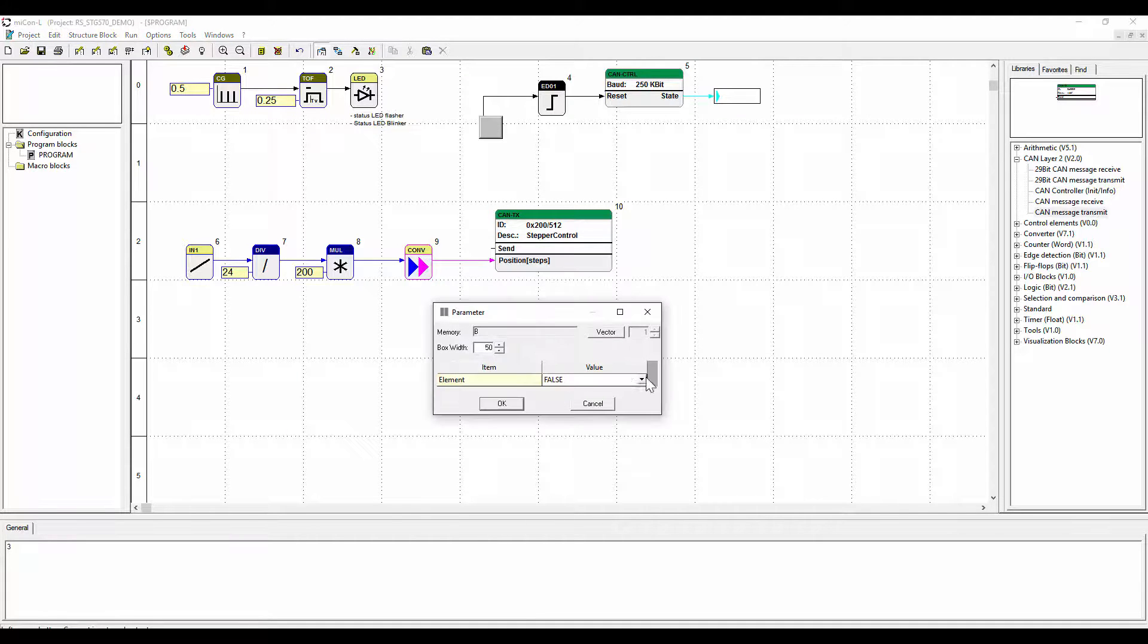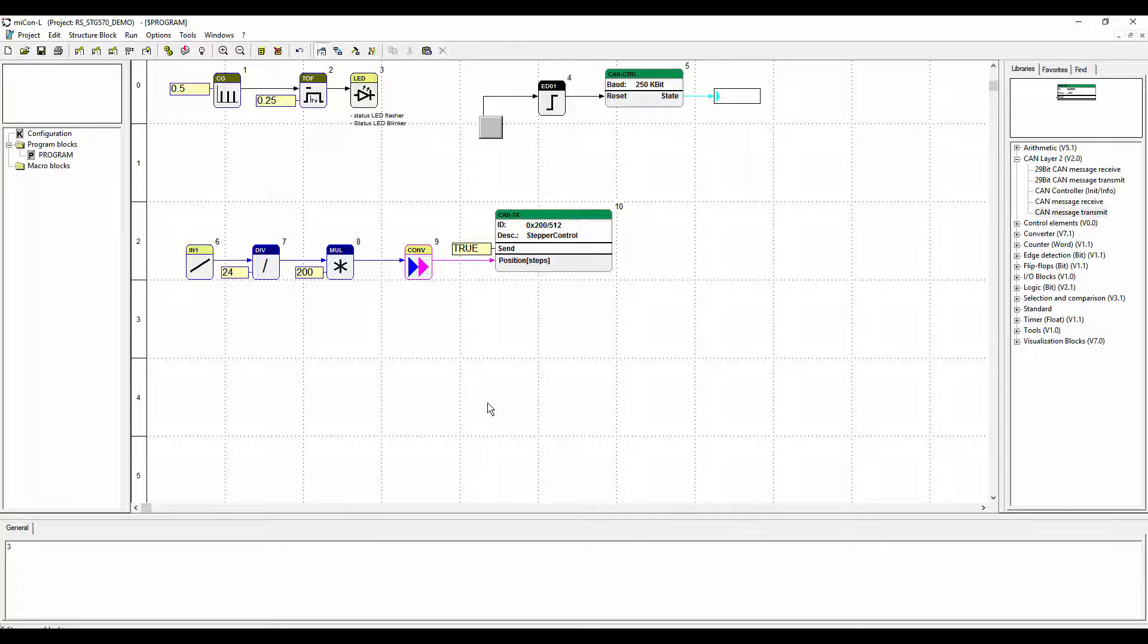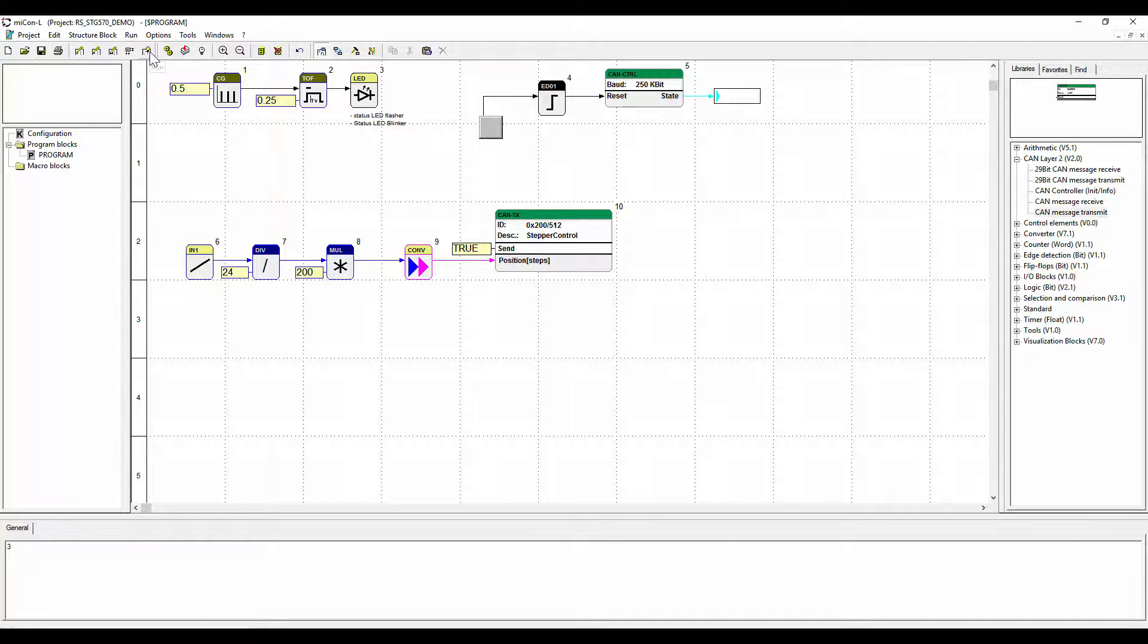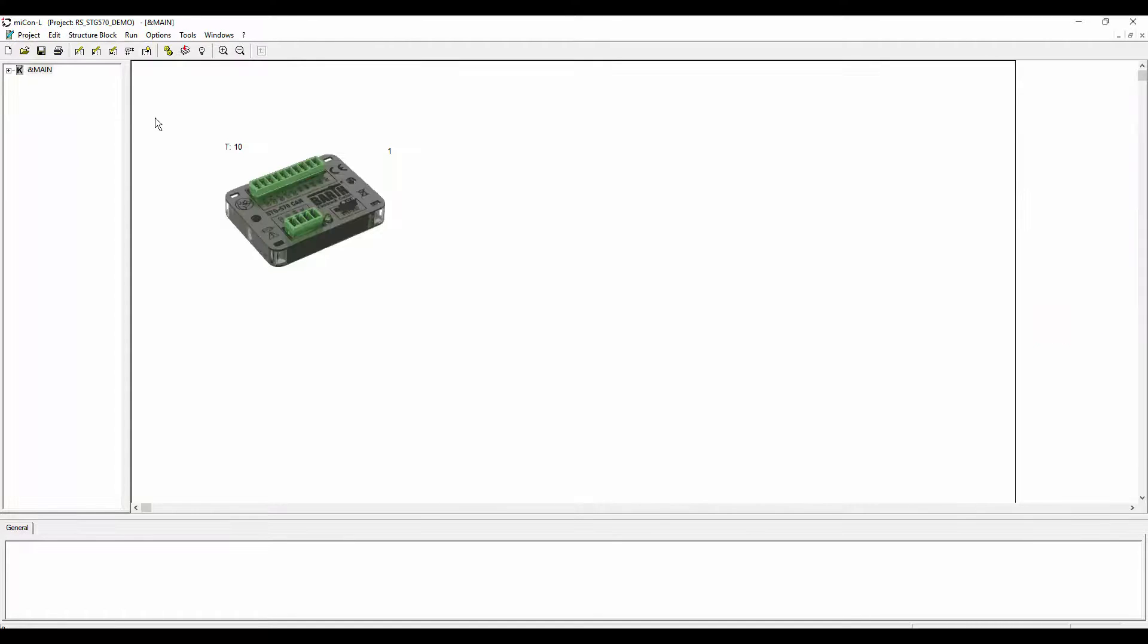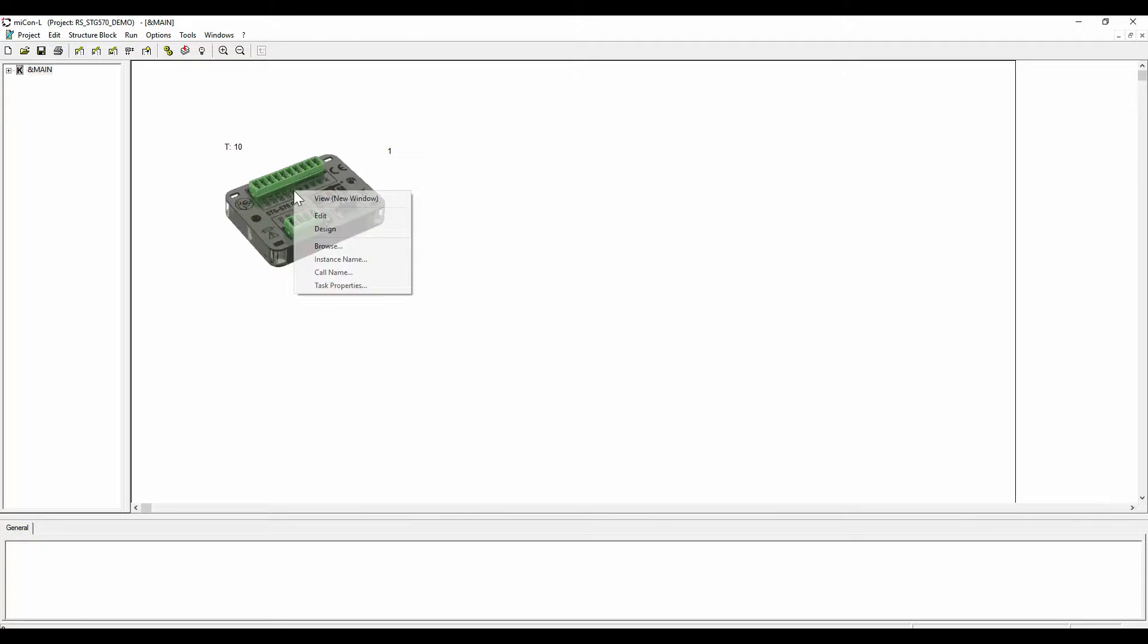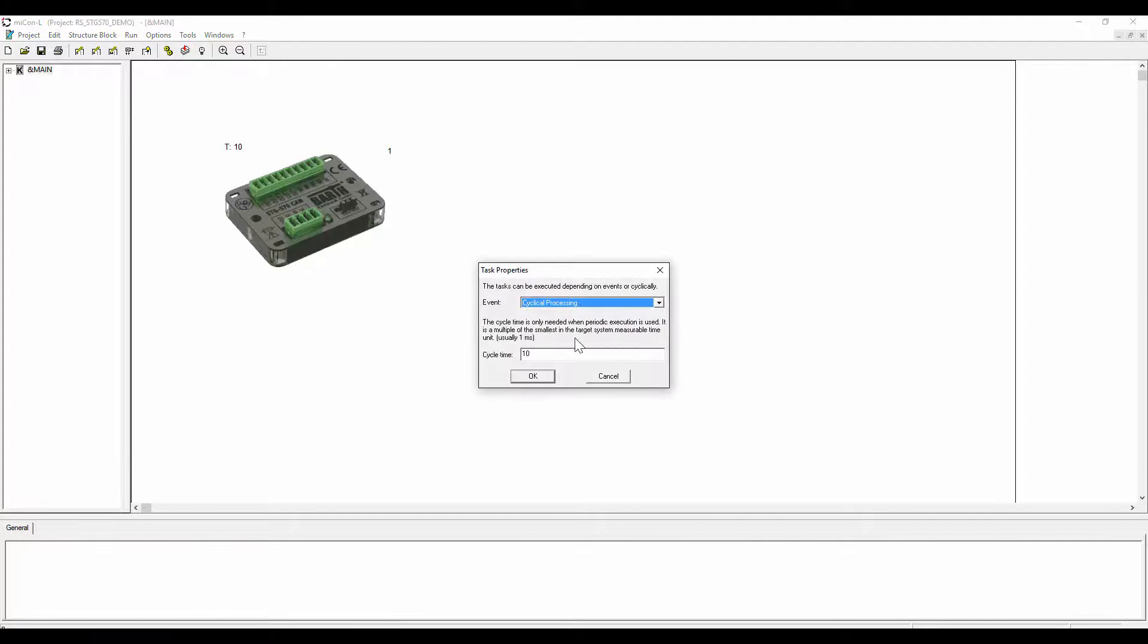Set the cycle time to 50 milliseconds to both programs, the one for the STG 570 CAN and also for the STG 700 step. Go into run mode and go into the configuration level. Right click on the controller image and go to task properties. Assign the cycle time of 50 milliseconds.